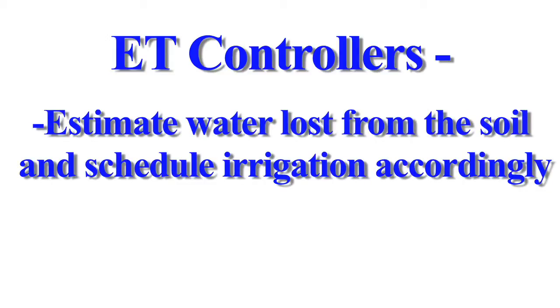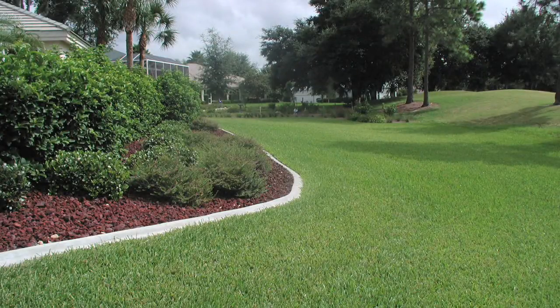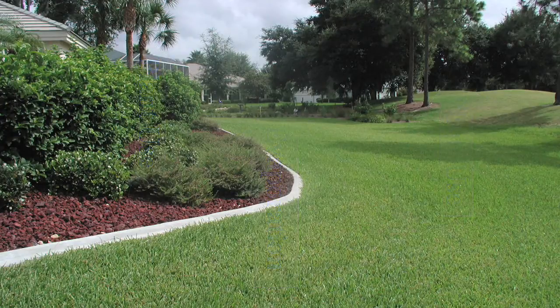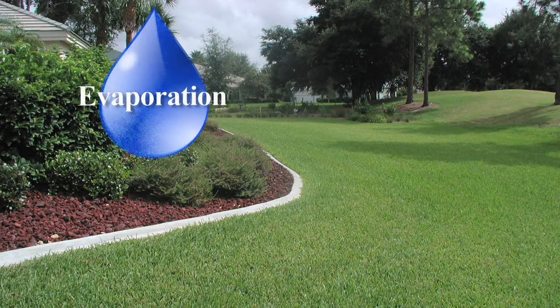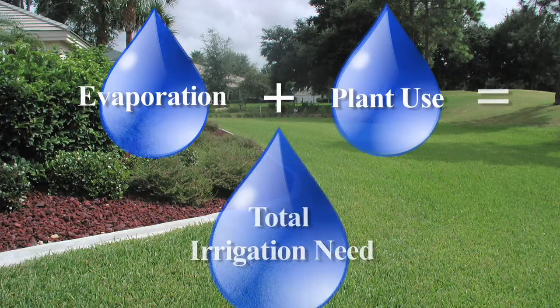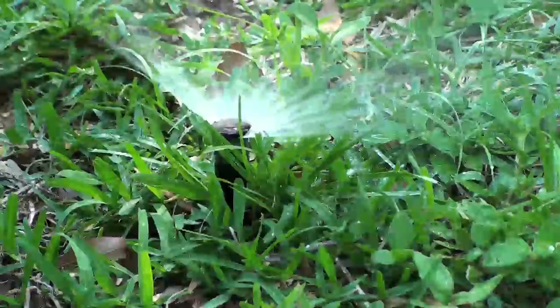Evapotranspiration irrigation controllers attempt to estimate or measure the loss of water in the root zone of the representative plant. For example, let us say that yesterday was a really hot day outside with a strong breeze blowing. Our soil is going to be losing a lot of water both due to evaporation and our plants. The ET irrigation controller will measure these weather conditions, estimate how much water was lost from the soil yesterday, and replace the amount that was lost by determining an irrigation system run time. Once the irrigation time rolls around, the soil is replenished and the process starts again for the next day.